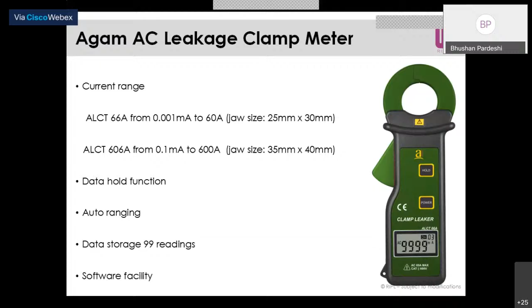Not only can one measure, one can hold that reading and check how much leakage is currently available in that system, and it can also record that leakage reading and store it in this device. This device comes with a data storage of 99 readings, so one can record 99 different leakage currents at different places, and through software retrieve them. So again, it helps in recording leakage readings in a system.